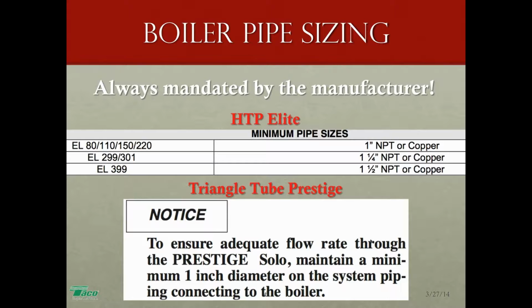They'll also tell you what circulator should be used as the boiler circulator. In many cases, they will in fact ship it with the boiler. That's the boiler pump. That's the pump you use as the boiler circulator on the boiler loop, and that's one of those things that's really not negotiable. John Scove asked a question: 6 feet of pipe or 6 inches on center T's? The spacing between those two T's, John, where the boiler loop connects to the header, no more than 6 inches or 4 pipe diameters. Ron Beck asked a really great question. What happens when the flow in the boiler is much greater than the flow in the indirect?